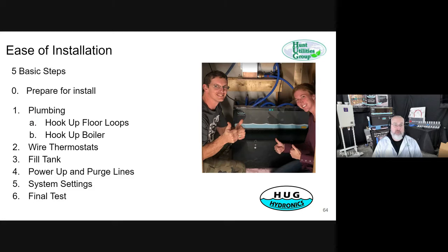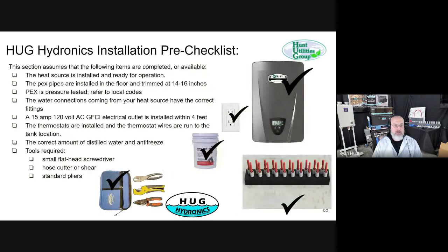So in a nutshell, we're hooking up the plumbing, hook up the floor loops, then you hook up the boiler. Then you wire the thermostats, then you fill the tank with water, and you power it up and you run the purge function to purge each line of air and fill it up with water. And then you go into the system settings and make sure that the thermostats are set up with the right pumps.